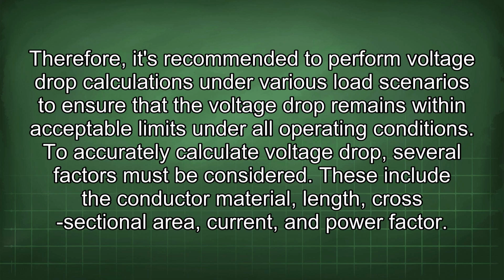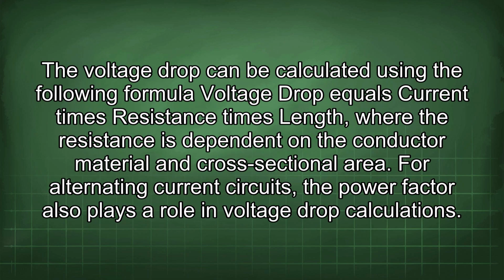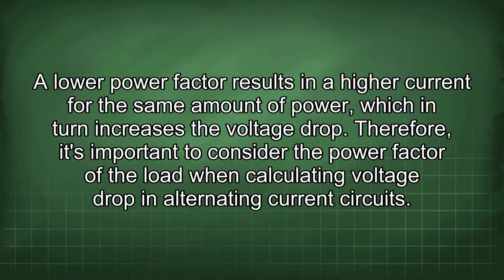To accurately calculate voltage drop, several factors must be considered. These include the conductor material, length, cross-sectional area, current, and power factor. The voltage drop can be calculated using the following formula: voltage drop equals current times resistance times length, where the resistance is dependent on the conductor material and cross-sectional area. For alternating current circuits, the power factor also plays a role in voltage drop calculations. A lower power factor results in a higher current for the same amount of power, which in turn increases the voltage drop. Therefore, it's important to consider the power factor of the load when calculating voltage drop in alternating current circuits.